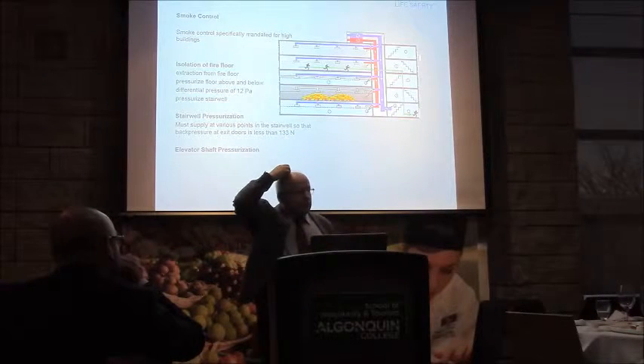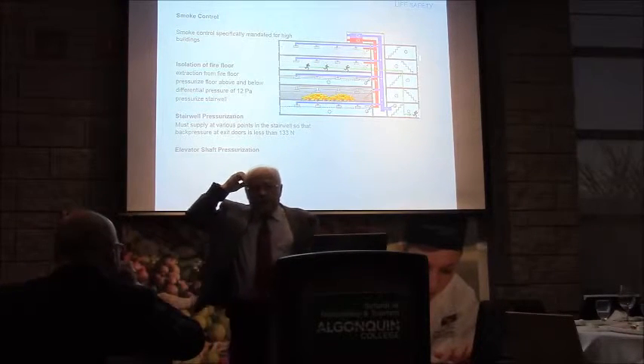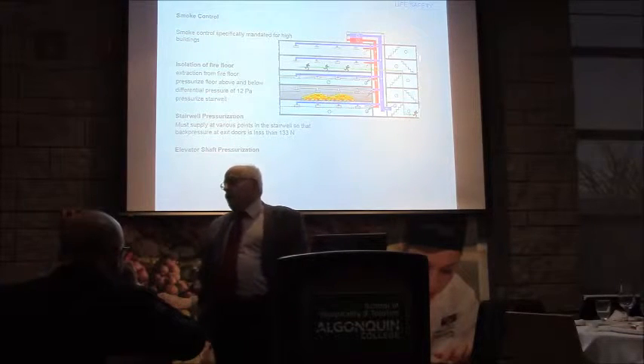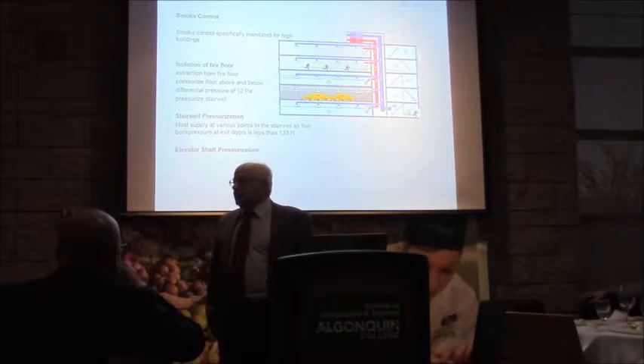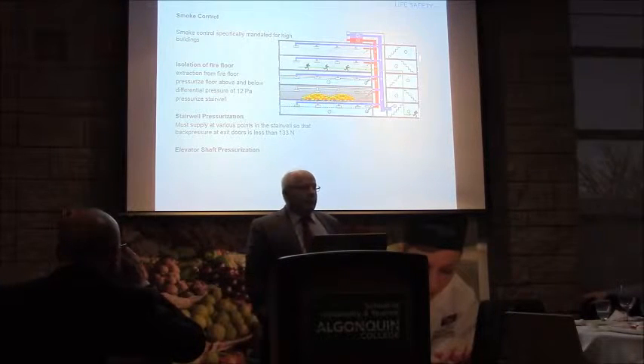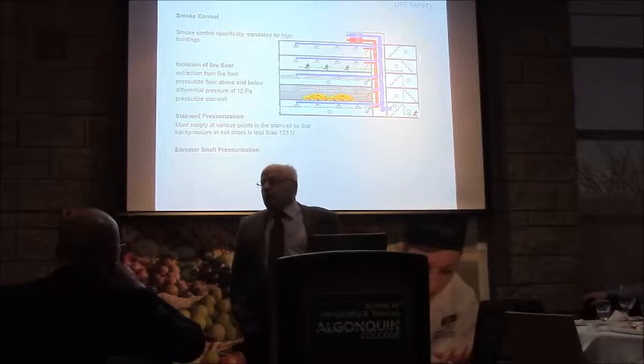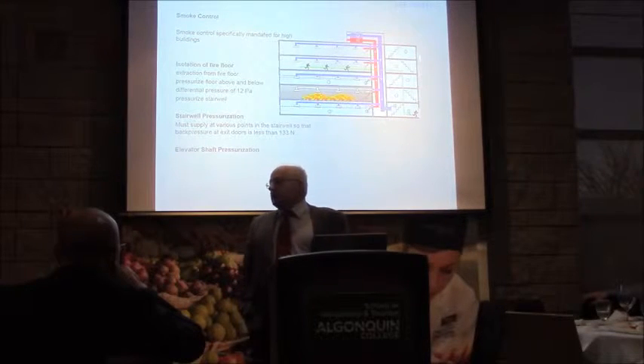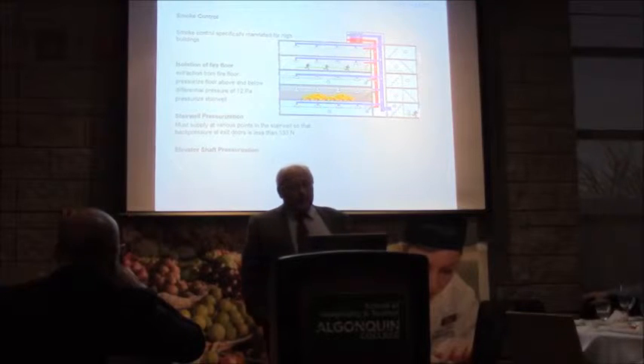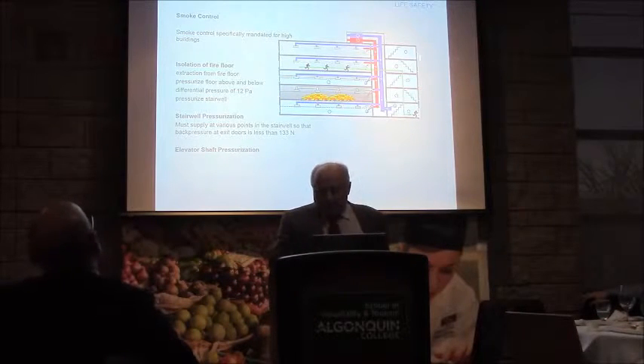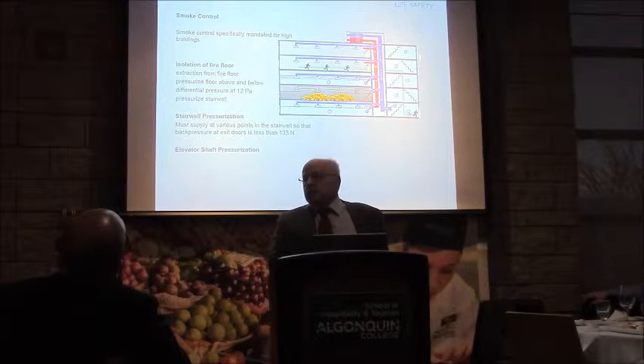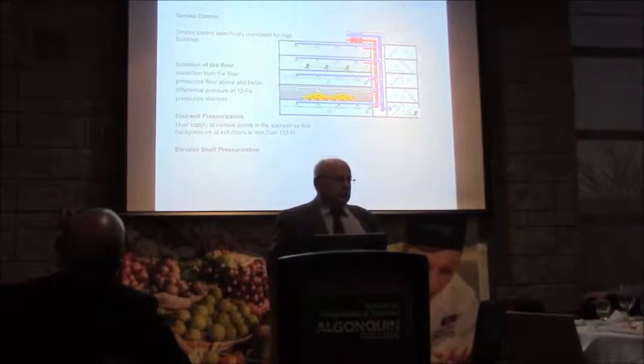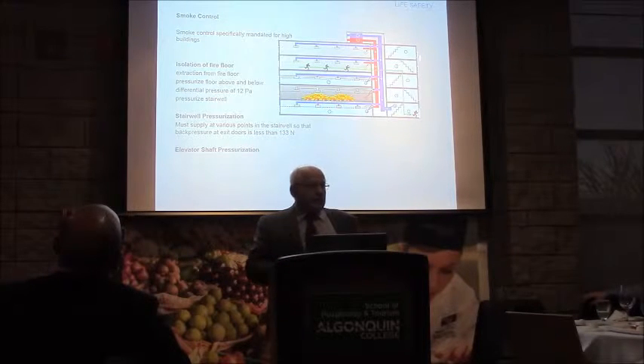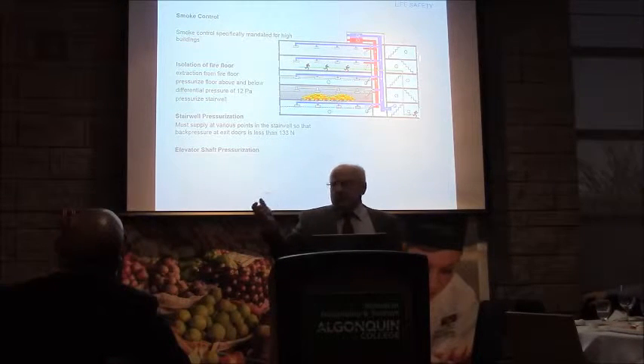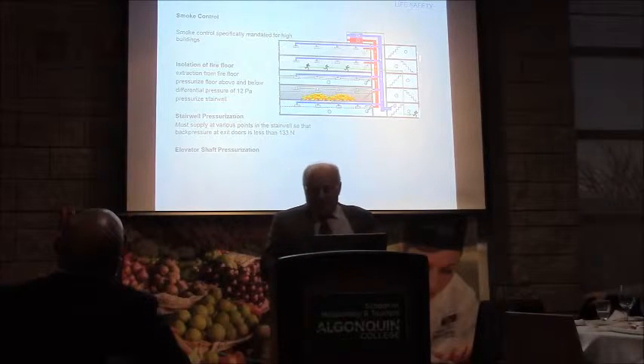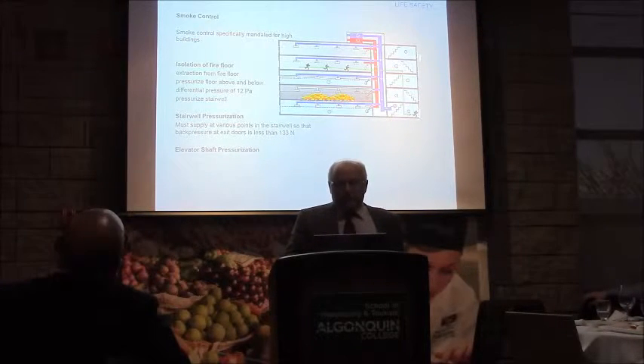Elevator shaft pressurization as a requirement is a real problem. The codes today, if you follow them explicitly, create a situation you can't achieve. The fire fighters' elevators, doors won't close because you're blasting so much air through that place that you just can't deal with it all. So various authorities allow alternative solutions where now we can put VFDs on these pressurization fans and crank them down to something a bit more normal. Otherwise, it doesn't work based on what the codes require.